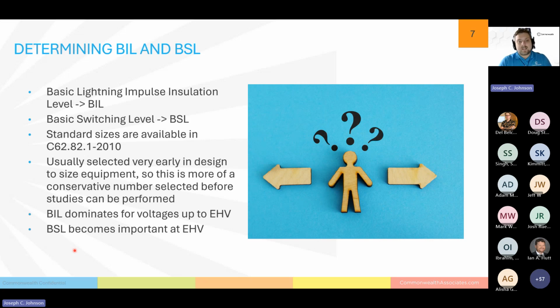Just as a note, the BIL is really the most important. It dominates for voltages up to EHV, before 345 kV, and then BSL becomes important beyond EHV or 345 kV and above. That's because the switching surges really scale with the voltage more so than the lightning will, and also the longer duration of these switching events leads to much more energy being discharged because of their wave profile, which we will look at going forward.